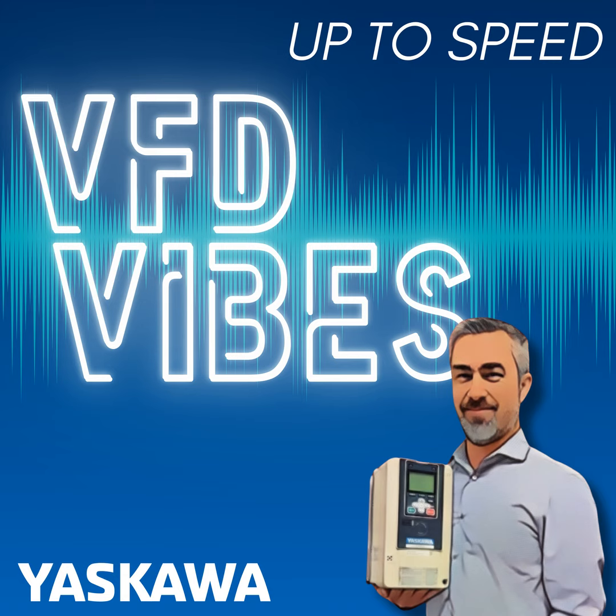Now, let's say in this case, it was an overvoltage fault. You went into U301, you see OV for overvoltage, very common fault, probably the most common fault you'll troubleshoot if you spend any time working on VFDs. Now, we also have in the U2 monitor group what we call a fault trace. What that is, is several metrics. It's a snapshot of exactly what happened on the last fault at the time of fault. And if you know how to interpret that data, it's going to make troubleshooting that overvoltage fault much easier.